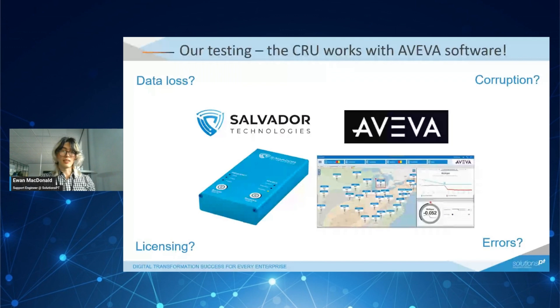Recently, my colleague Luke and I performed some tests with the CRU to verify its compatibility with AVEVA products like InTouch, Historian, and Enterprise licensing. We performed tests across multiple software versions with an InTouch application that, depending on the test, was logging data either to Historian or by itself. There was no data loss as a result of the backup occurring, which is very good — it proves that the agent does not interrupt any ongoing processes. One thing to note though: if you have anything running during the backup, only the data from the beginning of the backup will be saved. Anything that happens during the backup won't be saved as part of that backup, but it will be saved anyway in the next backup.